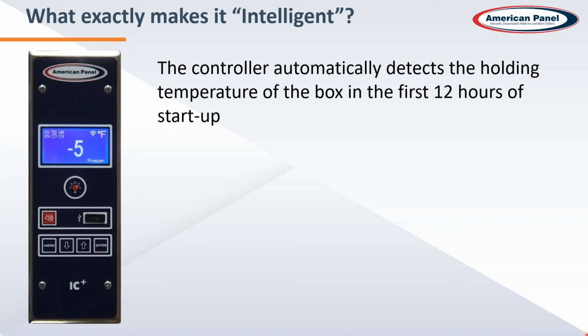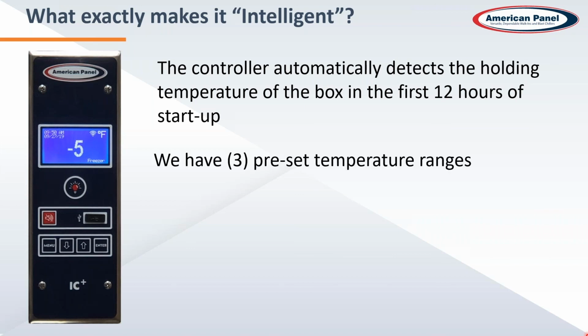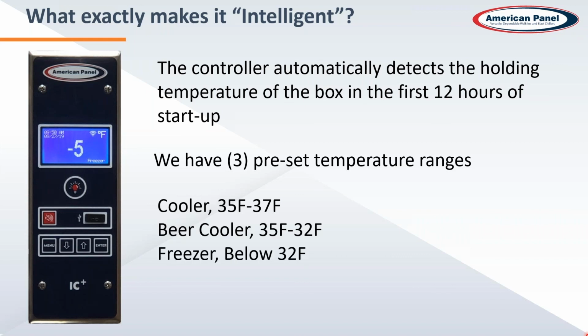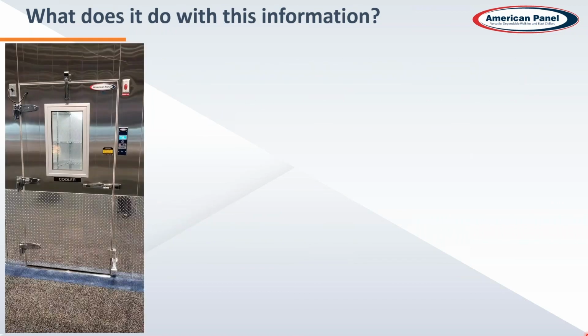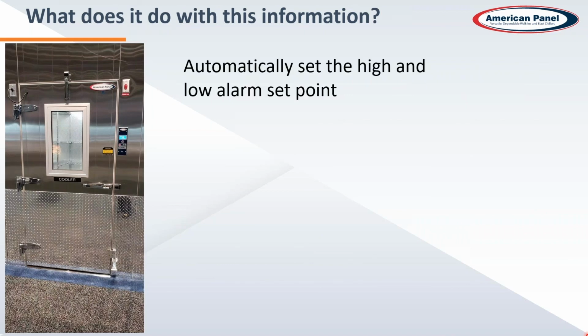So now with the IC Plus unit, the unit is smart and can figure out within the first 12 hours what that temperature is. So we have 3 preset temperature ranges that the system controller is looking for. Cooler in 35 to 37 degrees. If you're running a beer cooler, between 35 and 32 degrees, or if you're running a freezer, below 32. So what exactly does the controller do with this information? Well, first off, it'll automatically set the high and low set points of the temperature alarm on the system. So that way you don't have to program it or program it incorrectly or call in and talk to service or try to read the manual. The unit will automatically set the temperatures for you.